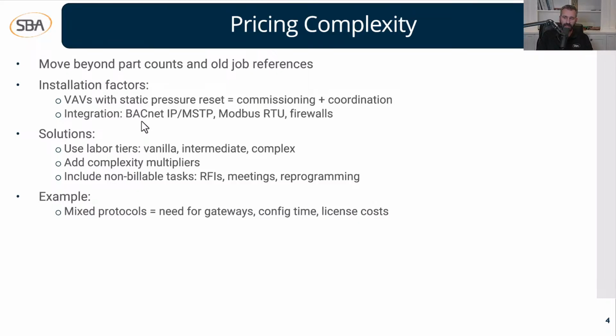Now integration - I touched on this already. Going from BACnet over IP or MSTP, or from Modbus to BACnet or LonTalk, you need to be aware of that. Your in-house technicians need to understand things like firewall rules and be able to talk with the IT professionals at the job site.